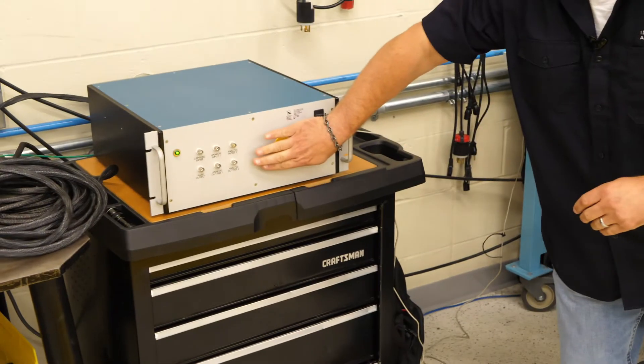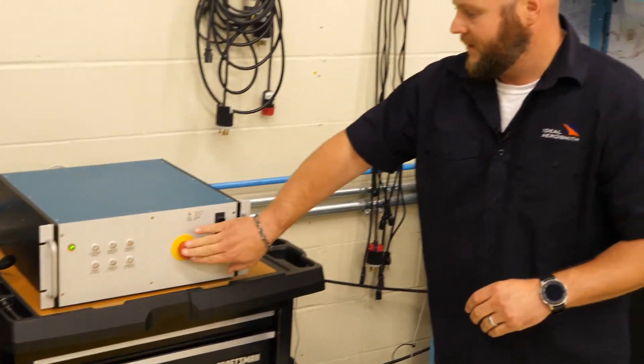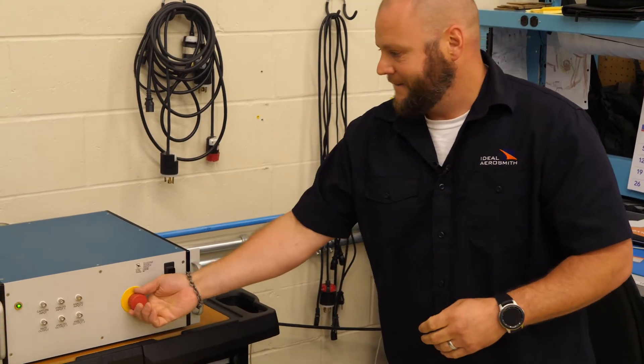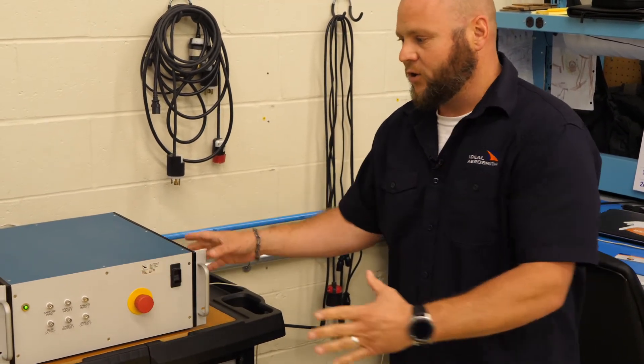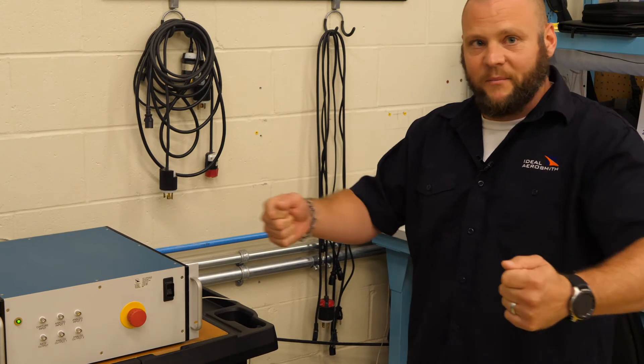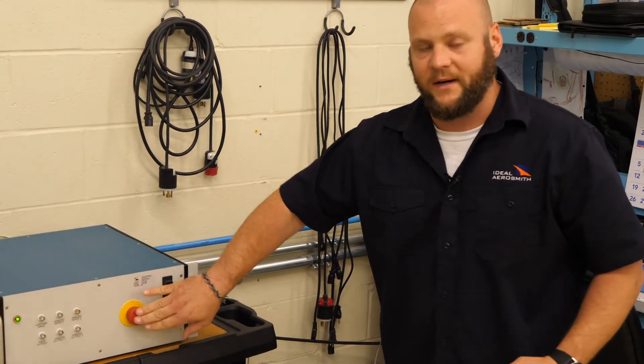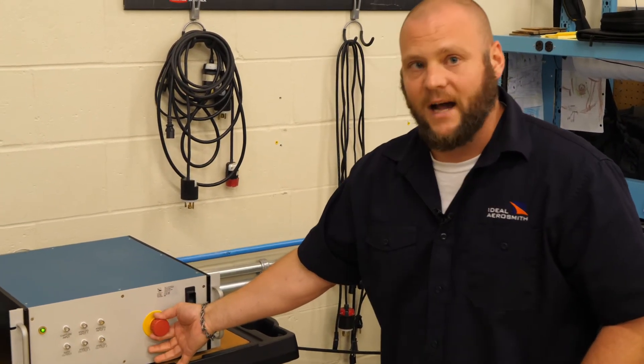So some things to look for is the emergency stop button. If this is depressed, you won't be able to release the brake or command a motion. Very possible that while uncrating this, someone picked it up and pressed it against their body and pressed that button in. So you want to make sure that that button is out.